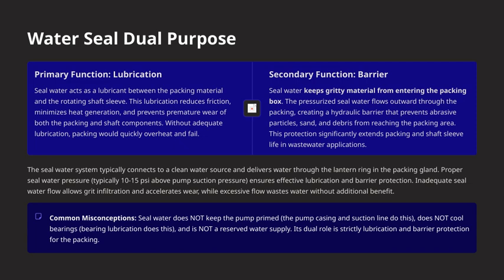Typically, the seal water system connects to a clean water source and is delivered through the lantern ring in the packing gland. Maintaining proper seal water pressure, usually about 10 to 15 psi above the pump's suction pressure, is key to ensuring both effective lubrication and barrier protection. If the flow is too low, grit can infiltrate and cause wear. Conversely, if the flow is excessive, it wastes water without providing additional benefits.